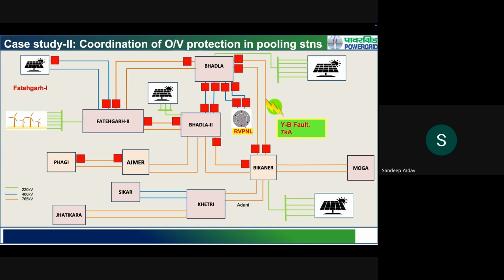This is case study 2, the same system that we talked about. There is a phase-to-phase fault on one of the 400 kV transmission lines, and whenever the fault took place, all these generators, be it WTGs or PV generators, stopped their generation or reduced their generation drastically. All these 400 kV and 765 kV transmission lines get lightly loaded, and this over voltage situation persists for a longer period of time. As a result, these transmission lines start tripping on over voltage protection one after another, and it causes a widespread blackout at the regional level.